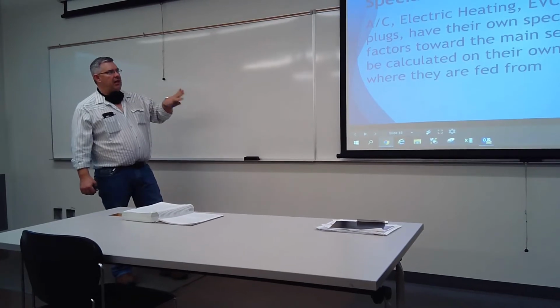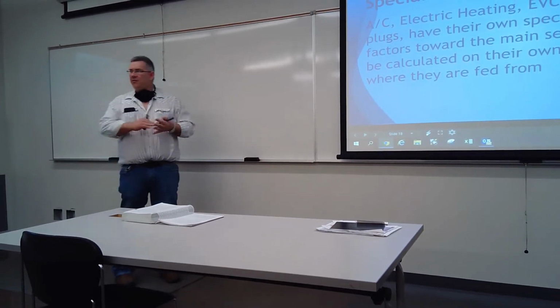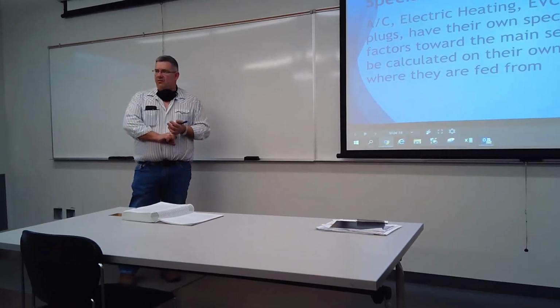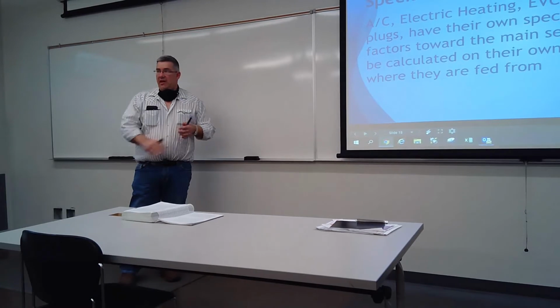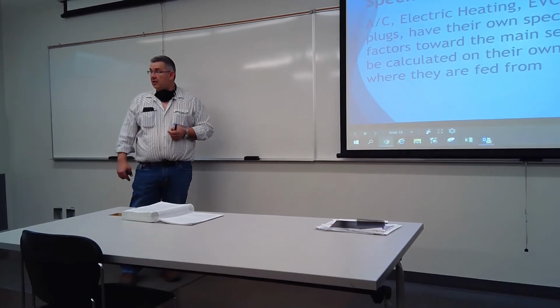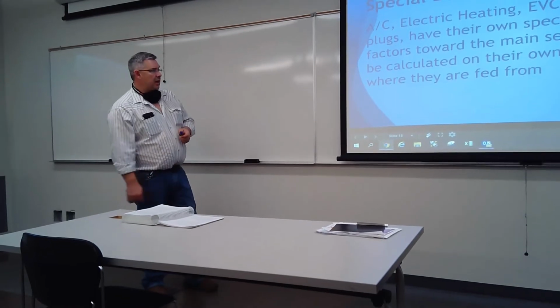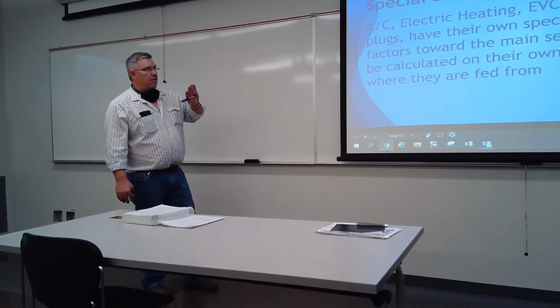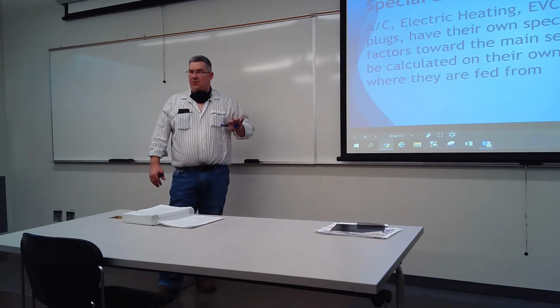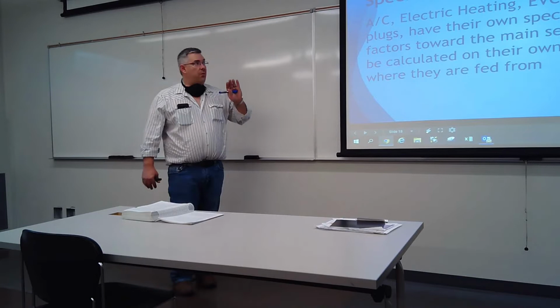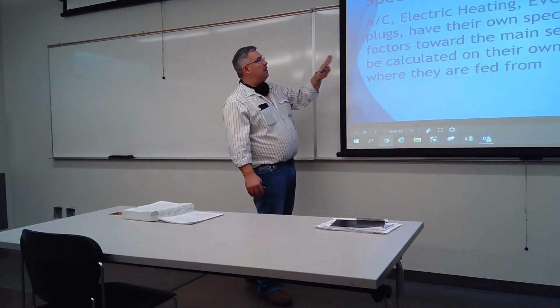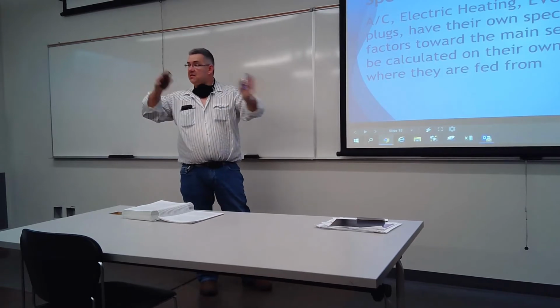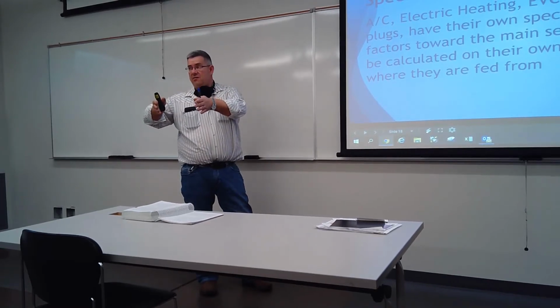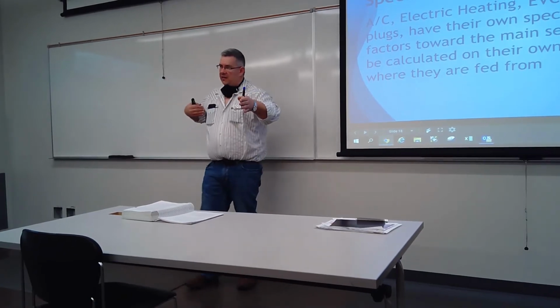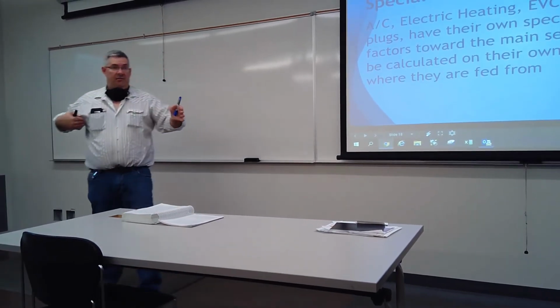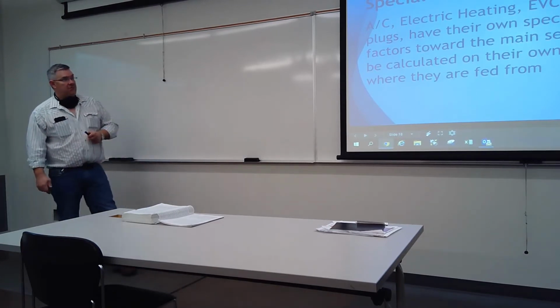When you have electric heating in apartment buildings, you really have to watch, because quite often it's for entry vestibules. You might have heaters running underneath the sidewalks to keep the ice from building up, things like that. Those aren't heating loads with individual thermostats in dwelling units. So when we look at electric heating in an apartment building, you have to take the stuff that's located in the apartments and treat it one way, and then all the electric heating that's outside the individual apartments and treat it its own way. Basically, it just means added at 100%.